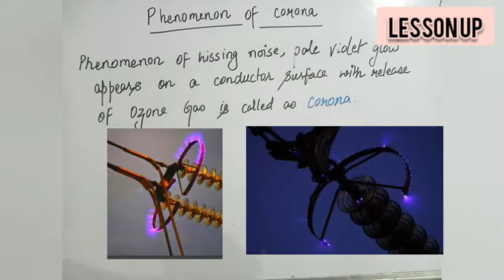The voltage at which this phenomenon takes place is called critical disruptive voltage. And what is critical disruptive voltage? The minimum potential difference required between the conductors to start ionization of air particles around the conductor surface is known as critical disruptive voltage, which is denoted as Vc. In a few books you can see it denoted by Vd, but here I am denoting it by Vc.